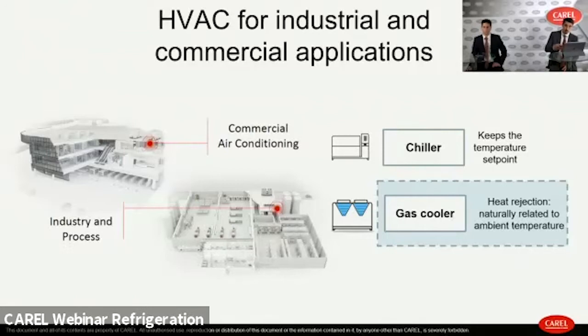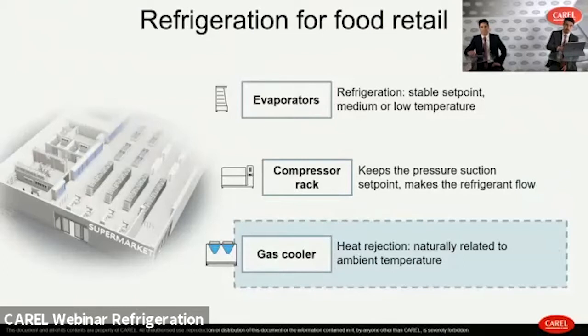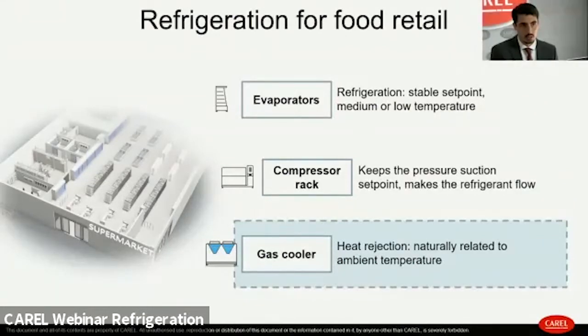We have something similar in refrigeration systems. This time the useful effect is in the evaporators, inside the cabinets where the food is kept: evaporators in cabinets, cold rooms, refrigerators. Here the CO2 evaporates to get the cooling effect. Then everything is processed by the compressor rack, which is responsible for keeping the pressure set point and making the refrigerant flow. And the part that interests us the most in this presentation is the gas cooler, where the heat gets rejected in the ambient. Again, there is a huge impact of ambient temperature on the gas cooler, in the same way as in HVAC applications.